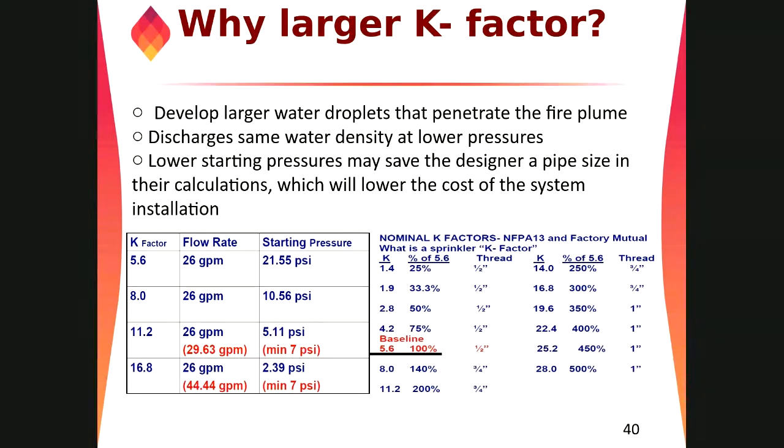Yeah, it's the design of the system, and once after design, the consultant wants to review that the correct type of sprinkler is installed. They might go to the site and look at the deflector. At the deflector, there is a stamp of the K factor, the one we discussed in the previous class regarding SIN, right? Sprinkler identification number. Yeah. So during commissioning of the system. Yeah, during commissioning and acceptance test, they will see that one. So with the K factor, we have to start the basics of sprinklers, how much water we need.